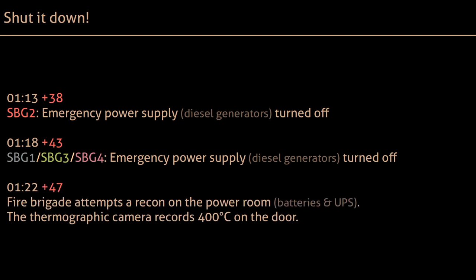The fire brigade, 47 minutes later, attempted a recon on the power room, where the batteries and the uninterruptible power supplies were. The thermographic camera records 400 degrees in the room. Of course, they couldn't get in. And at this moment, the fire brigade just learned that it's actually lead batteries.